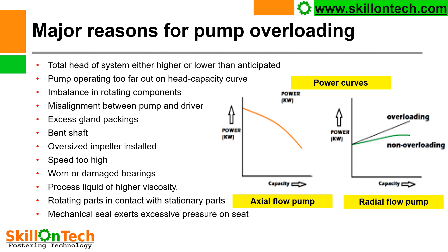Here in these two curves you can see: in an axial flow pump, capacity is on the X axis and power is on the Y axis. Power drawn is more initially in axial flow pumps and then it drastically comes down. But in the case of radial flow pumps, power increases progressively like this.